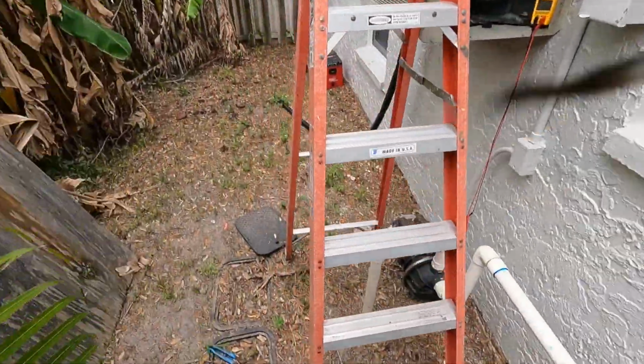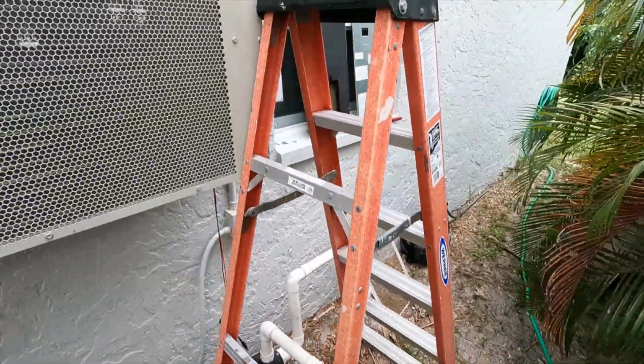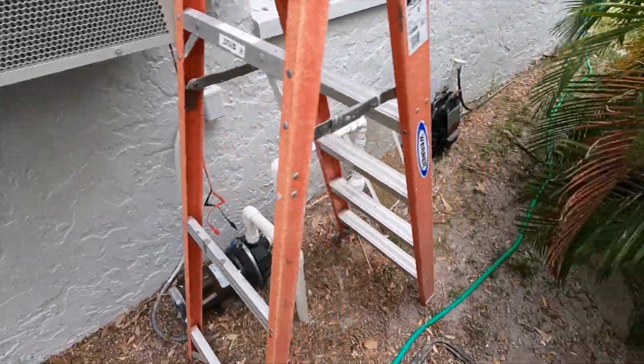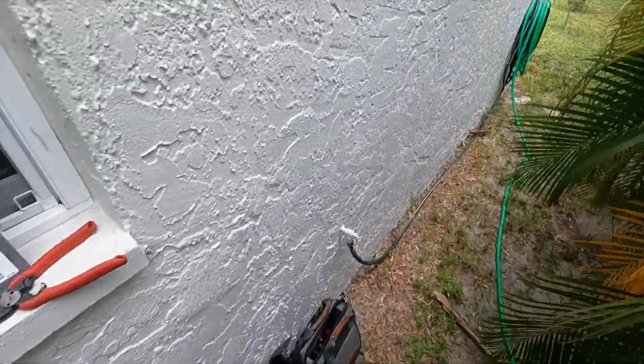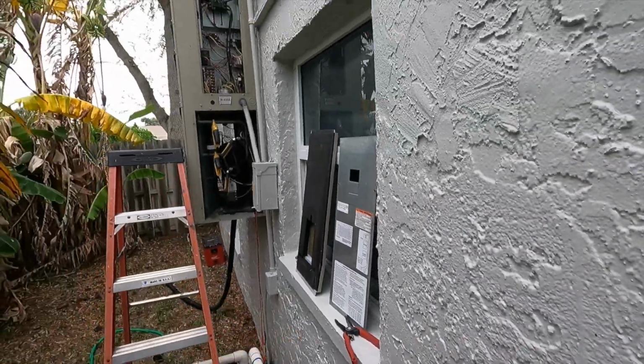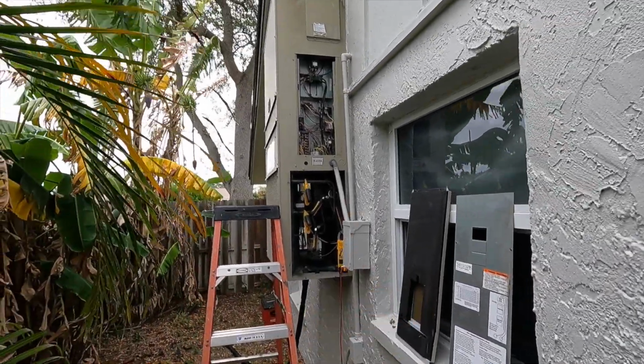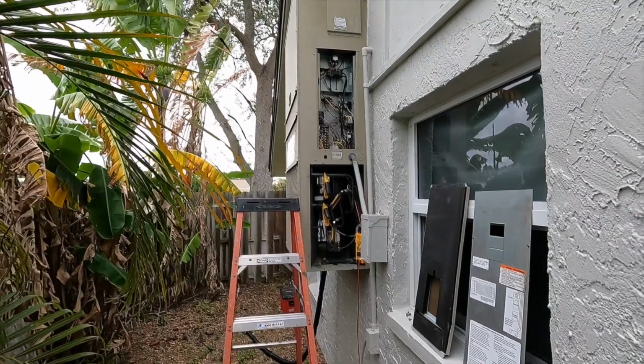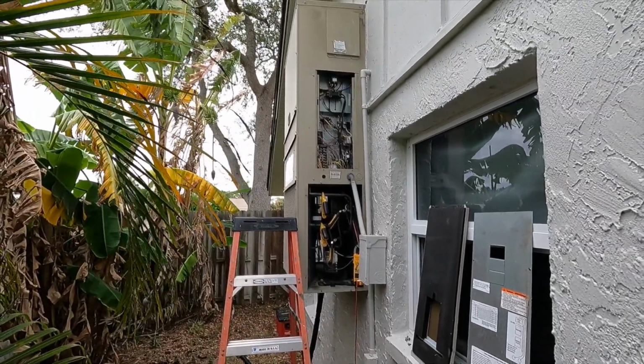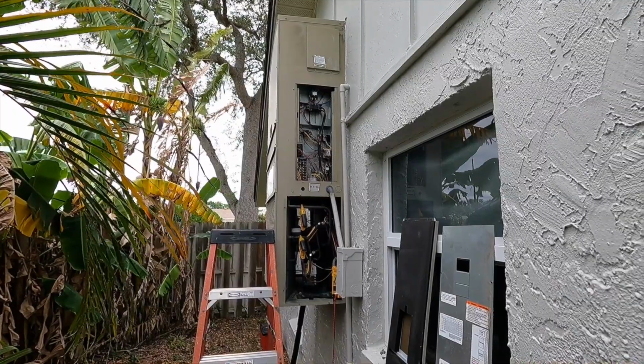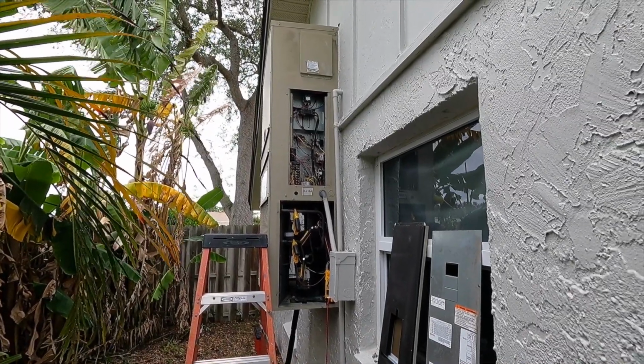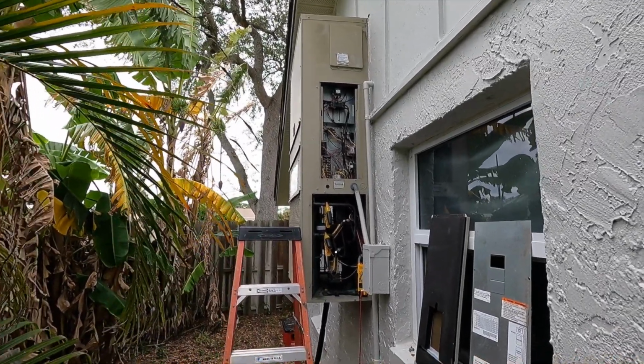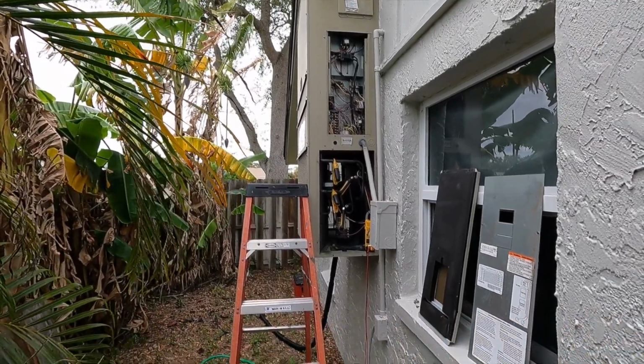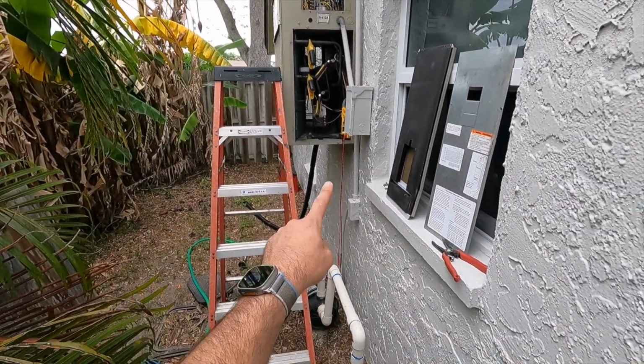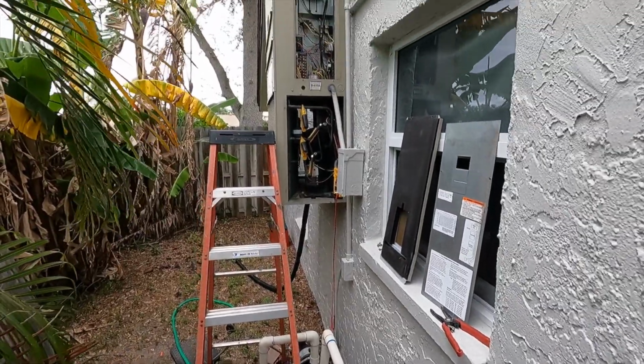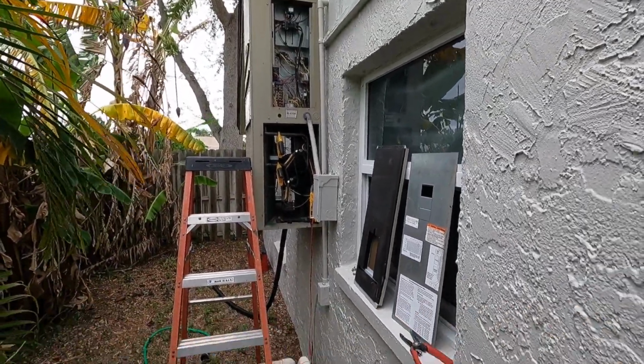I don't like dead time. I don't like standing around waiting for time delays to kick on and whatnot. So if there's something I can do in the meantime, I do it. So I know that once we get done with that lock rotor amp check, all my measurements for the most part outside of the heater have been checked, and I'm going to want to clean that condenser coil, clean that evaporator coil, take a look at the condition of the blower wheel. I don't believe it's going to have a capacitor, but we'll check. Actually, it should have a capacitor, but it should be up there with the blower. So we'll check that. Check the drain pan, clean it up. I got to grab my wet vac so we can vacuum out his drain line here, make sure we don't have anything clogging up. Yeah, I don't like dead time.